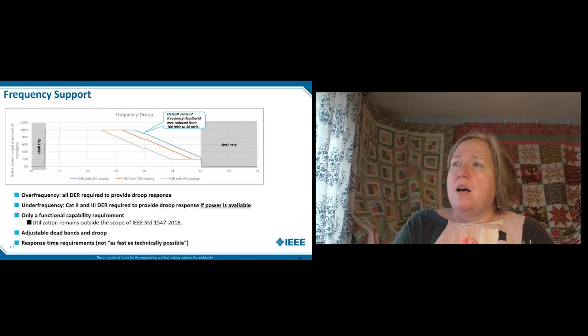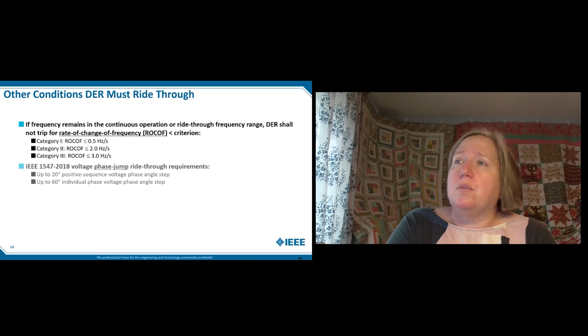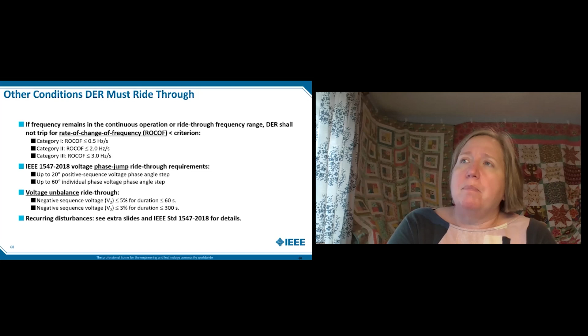Other conditions DER must ride through. There are rate of change of frequency requirements based on the category. If you look at category 3, it can go up to 3 hertz per second change of frequency and has to ride through it. There are voltage phase jump requirements, and there are voltage unbalance requirements. If there are recurring disturbances, there's material in the standard about that.